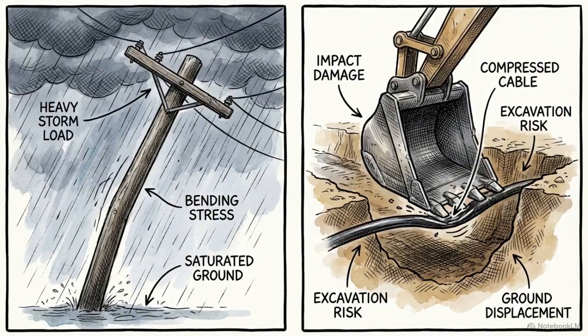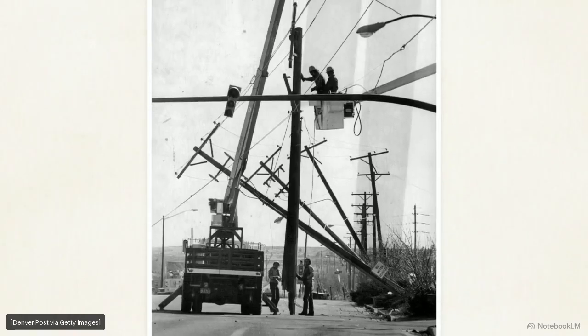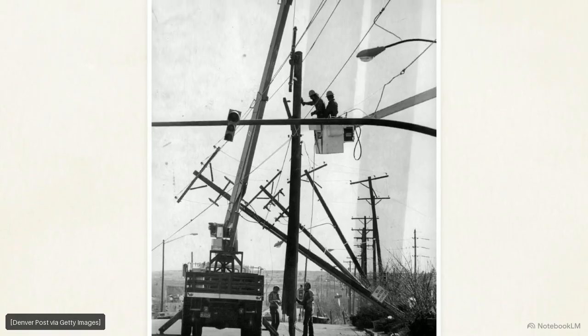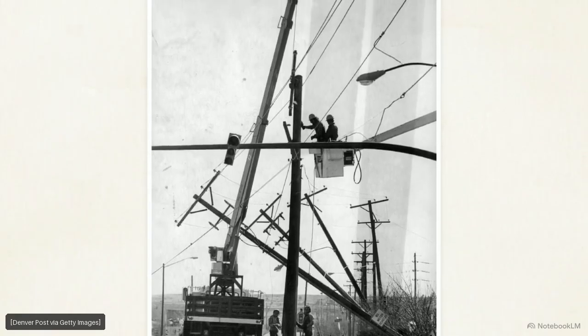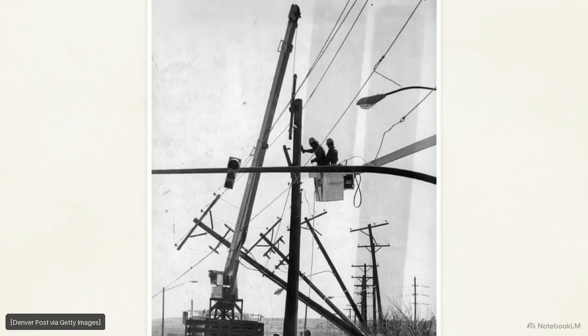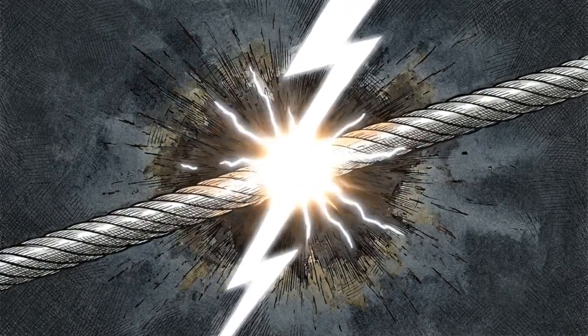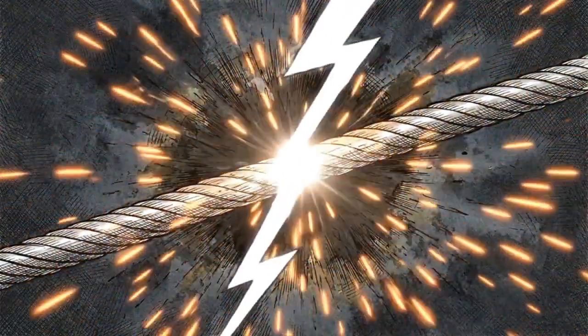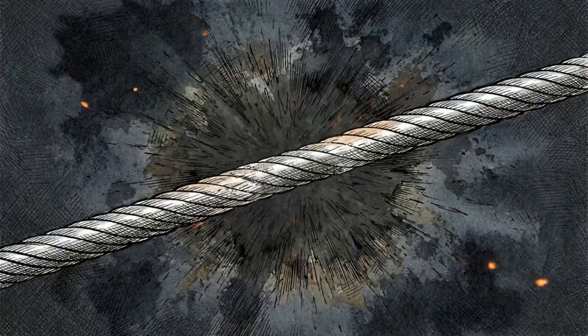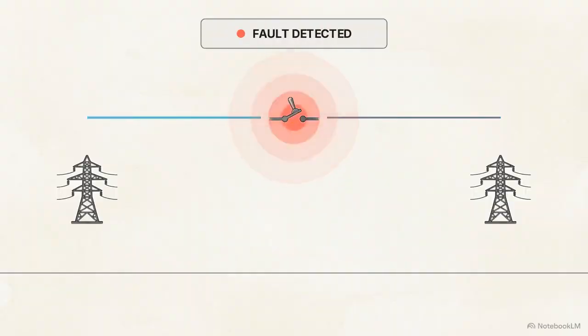These physical differences also dictate exactly how the two systems operate under stress and what happens when they break. Overhead lines are constantly exposed to the elements. They get struck by lightning, blown over by high winds, and tangled up in falling trees. However, up to 90% of these issues are temporary faults. If a lightning strike causes an arc, a circuit breaker trips to cut the power. In a fraction of a second, the surrounding air deionizes, the breaker automatically recloses, and the power flows again.